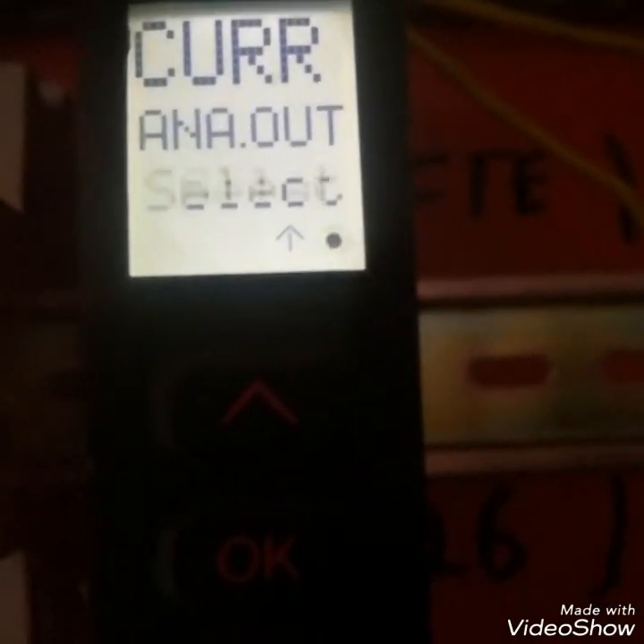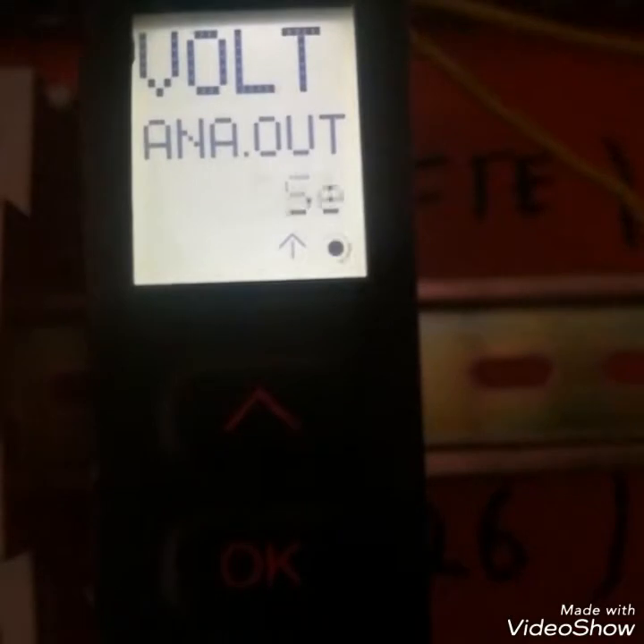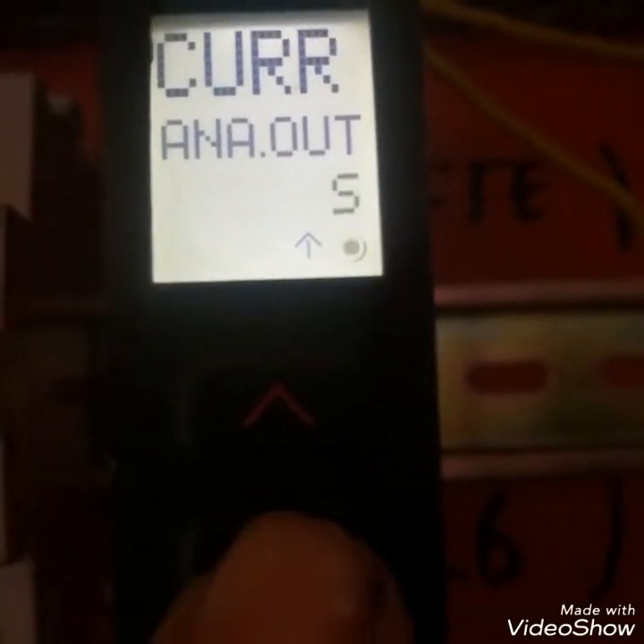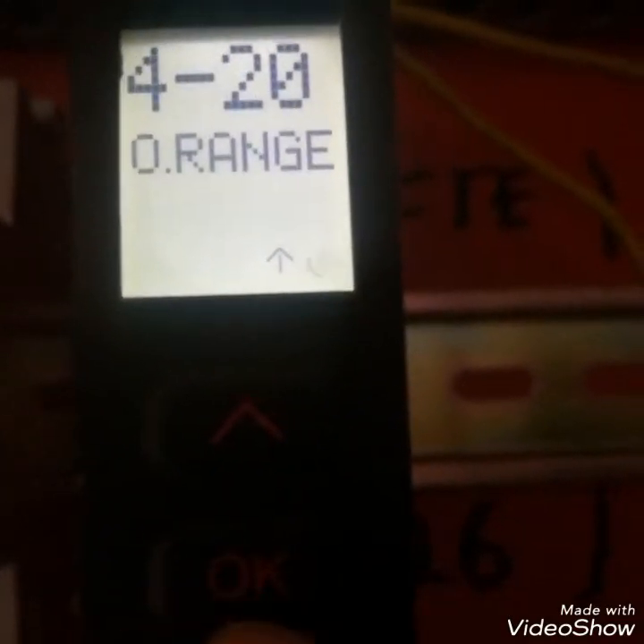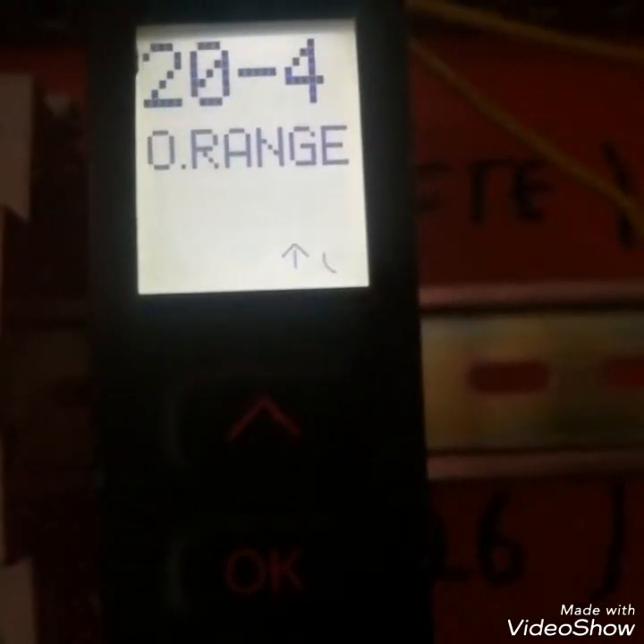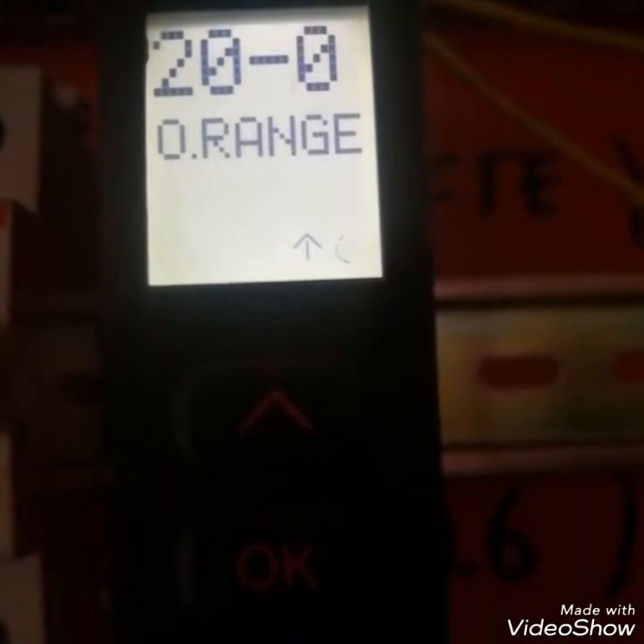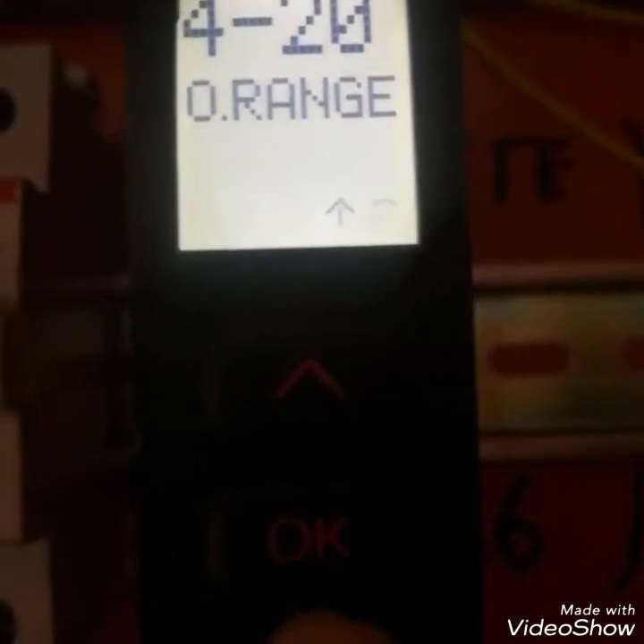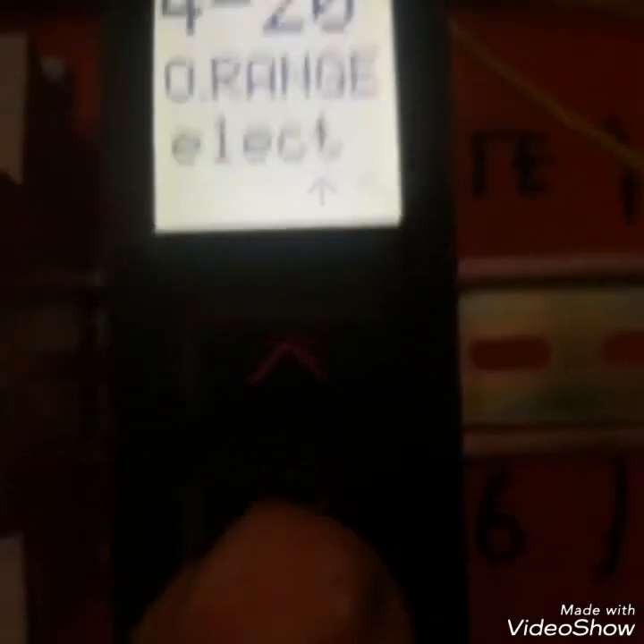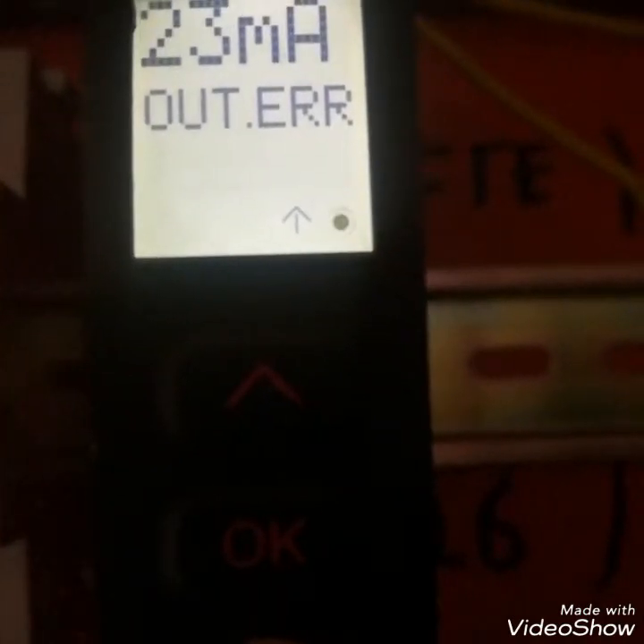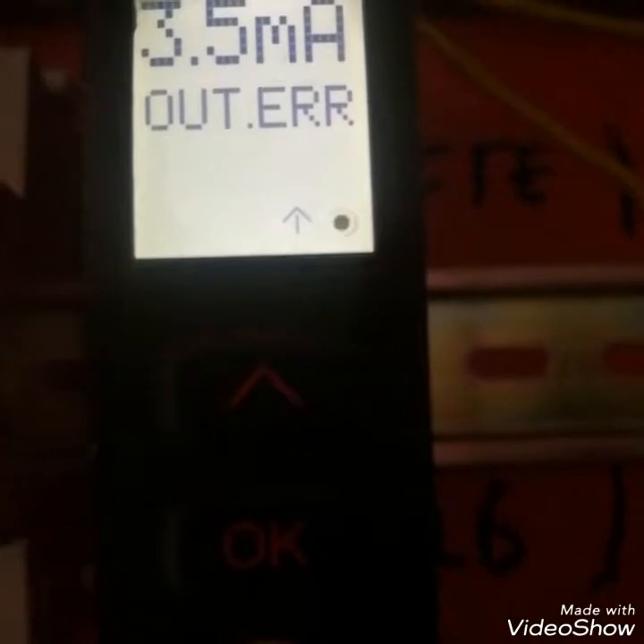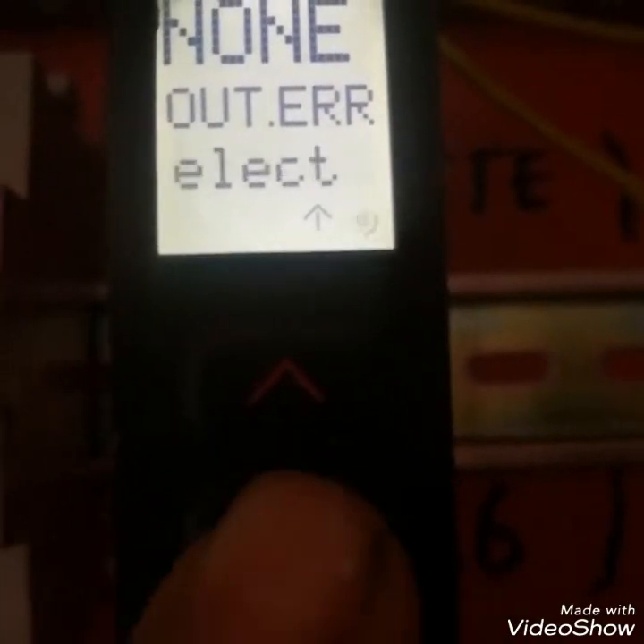Analog output is current or volt. We are taking current, which is 4 to 20 milliamps. We can change the range to 0 to 20, 20 to 4, or 20 to 0 as per requirement, but here our requirement is 4 to 20 milliamps. Out error: if there is an error, what will be the output current? We use none.